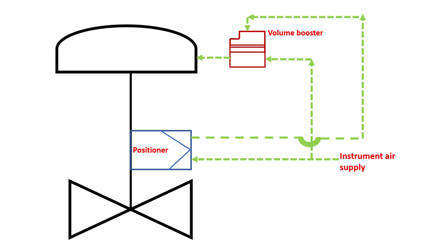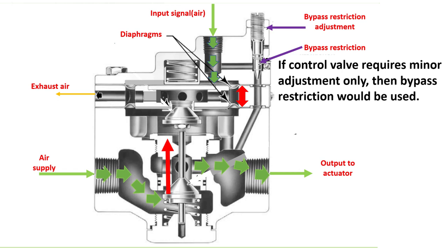What is the purpose of the bypass restriction component? For example, if your control valve is at 50% operation and the setpoint changes to only 50.5%, the input air signal will increase by only 0.5%. This small signal will not have much impact on the volume booster, and the volume booster does not necessarily require small signal amplifications. So this small input signal proportional to 0.5% will pass through the bypass restriction and go directly to the actuator without going through the diaphragm. This is the use of the bypass restriction.